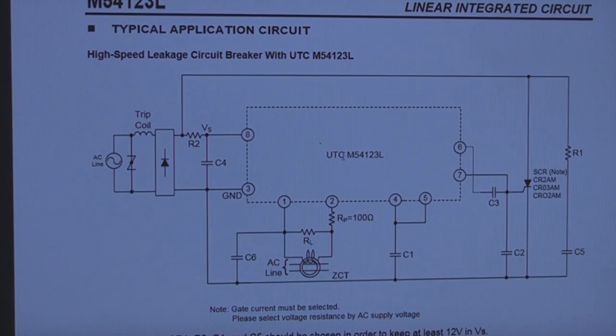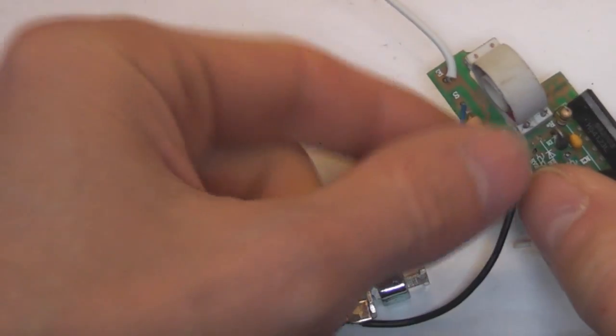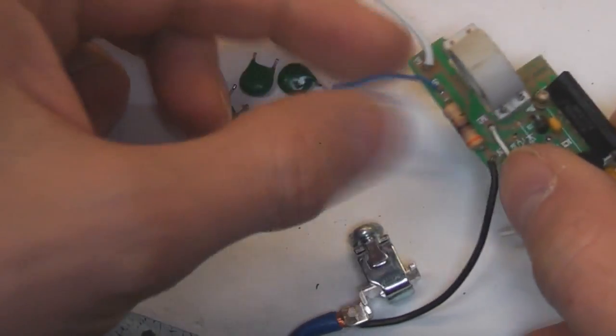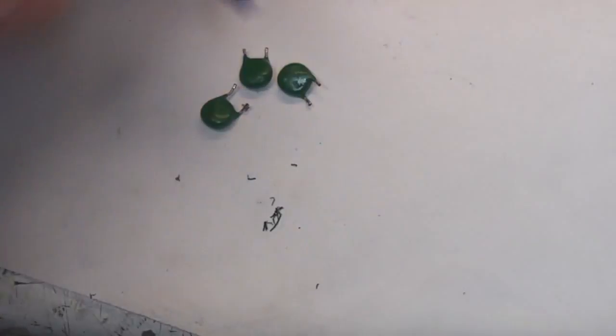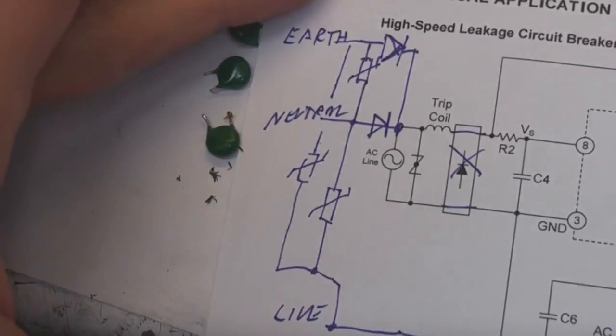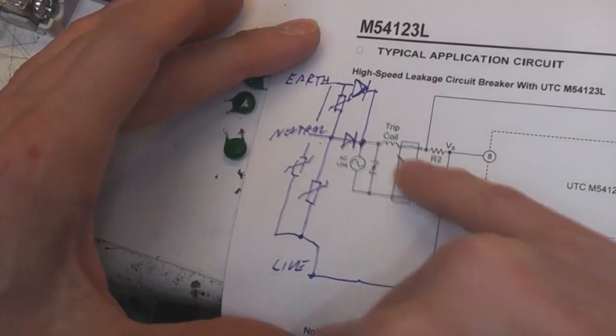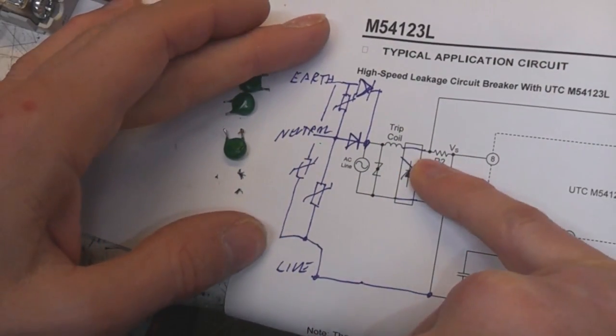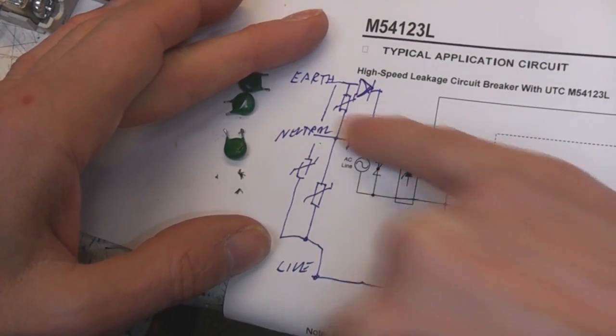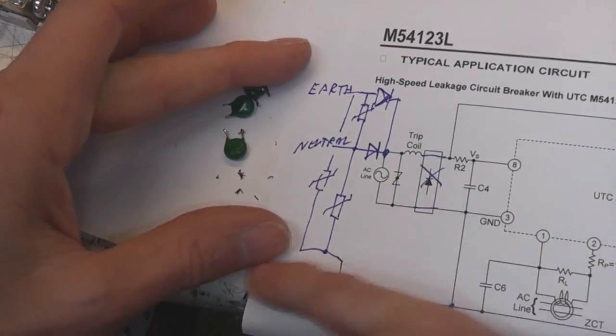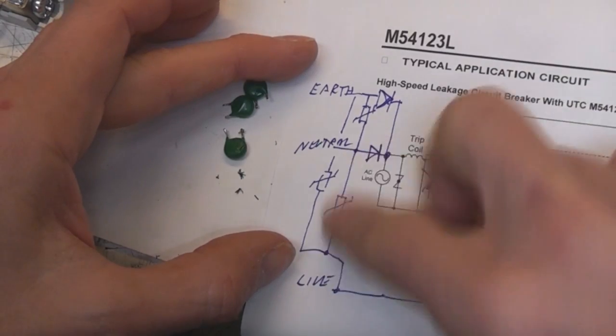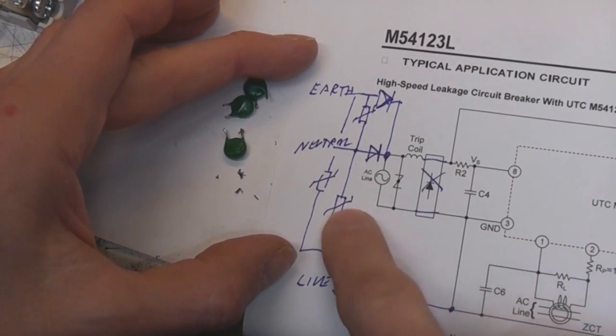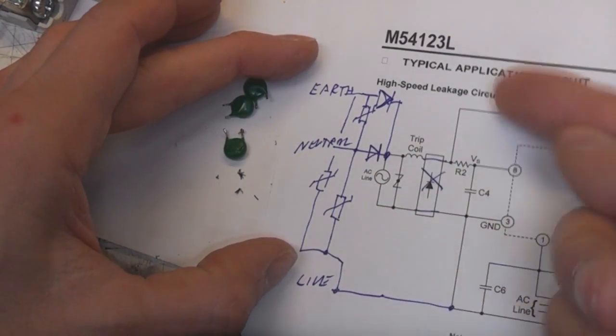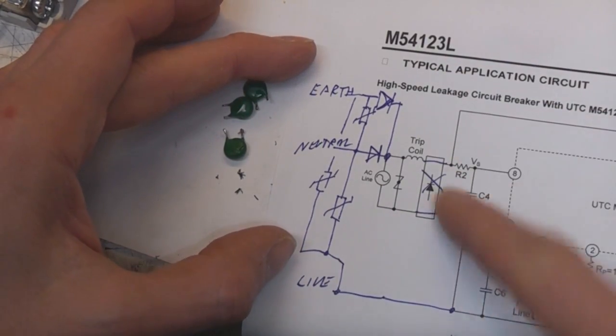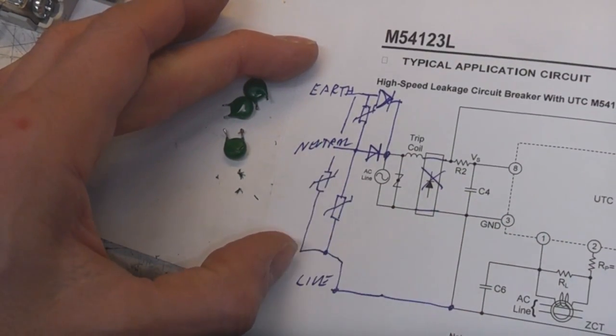So it's a fairly simple circuit in there. Just taking the RCD board out to take a look at what they're actually doing with this earth, and yes, it is very straightforward. If you take the reference circuit, they're not using the bridge rectifier, they're using a half-wave rectifier, and we've got a supply from both the earth and the neutral, and these 3 MOVs connected in triangle form across those 3 pins to provide protection for any transient. So yes, the earth is just a backup supply, so the thing will still trip if the neutral fails.